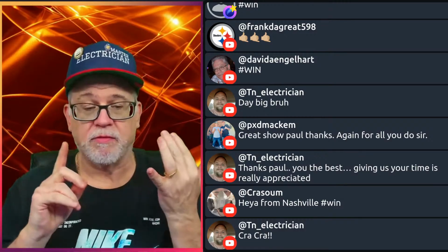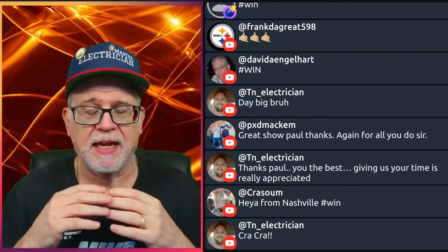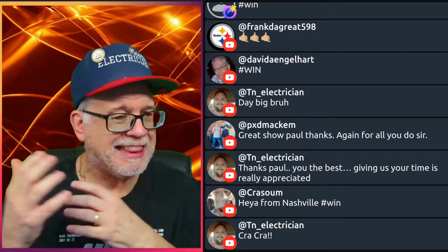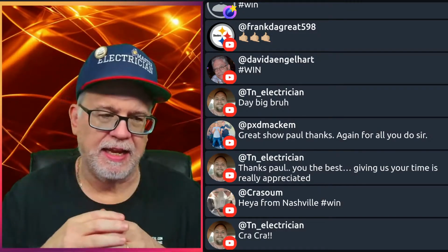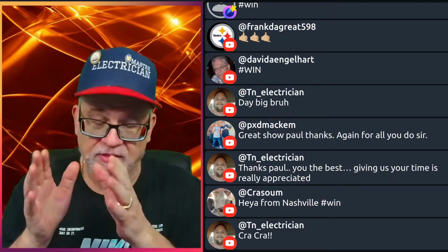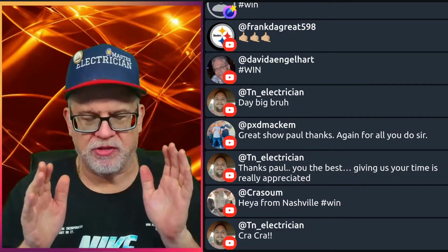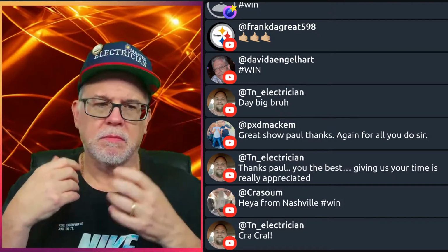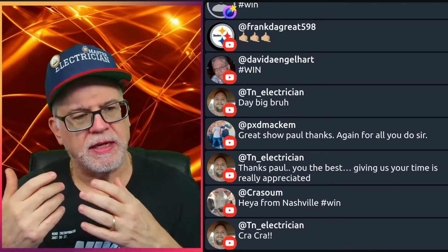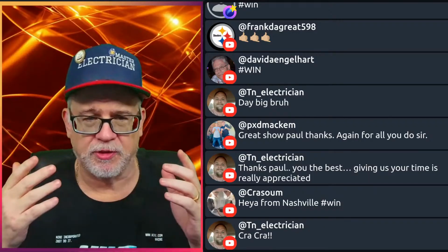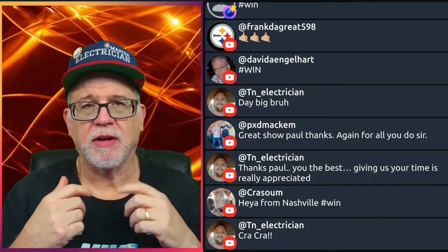And they were doing it, documenting it. They were doing okay. The problem is they'd never find anything wrong. So I had them give me their images and I looked at it, and I asked them to take some pictures of the same exact location, not through thermal imaging. And I found so many problems with what they were submitting and how they were doing it. And there is a right way and a wrong way to report something. It's called tactfulness. And we used to train this all the time.